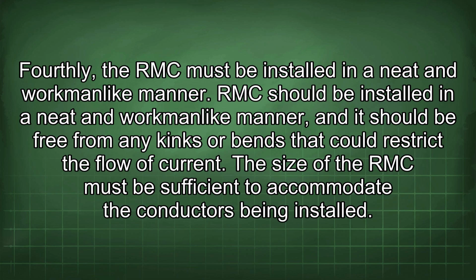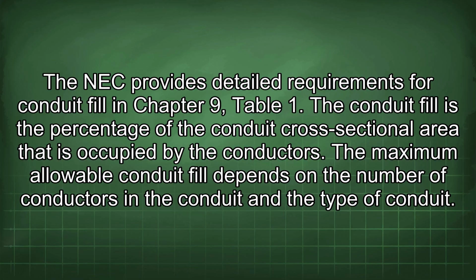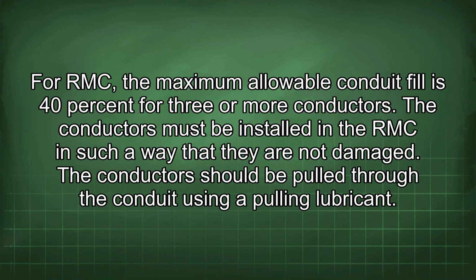The size of the RMC must be sufficient to accommodate the conductors being installed. The NEC provides detailed requirements for conduit fill in Chapter 9, Table 1. The conduit fill is the percentage of the conduit cross-sectional area that is occupied by the conductors. The maximum allowable conduit fill depends on the number of conductors in the conduit and the type of conduit. For RMC, the maximum allowable conduit fill is 40% for 3 or more conductors.